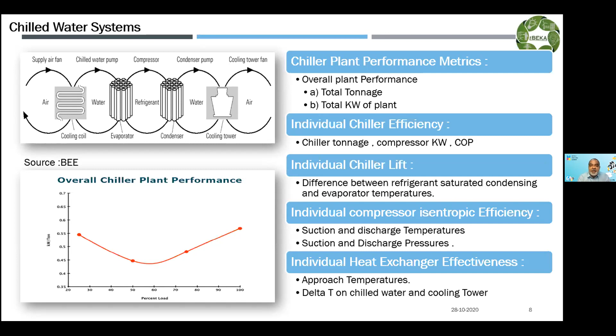The water management is one. Then entering chilled water temperature set point is very, very important when we talk about the temperature set point. Eliminating all refrigerant leaks, maintaining the design water flow rates, removing non-condensable gases and moisture, then calibrating and maintaining temperature sensors, because it happens that temperature sensors are not calibrated, thermo wells are not maintained, and finally my chiller is going to work based on the sensor signal, and many times it happens that there is an energy loss.